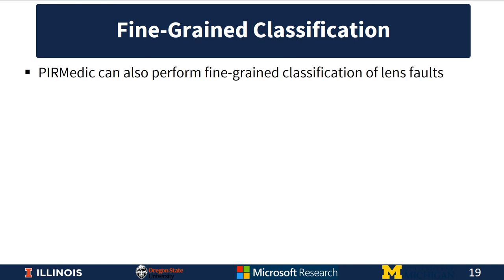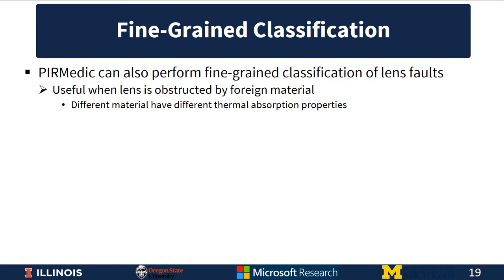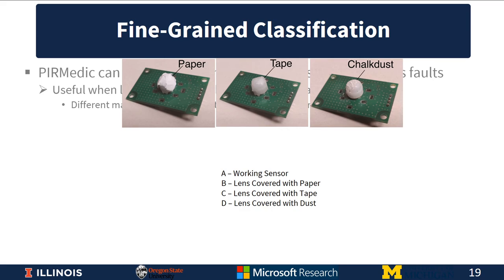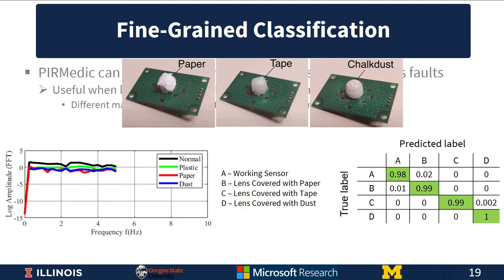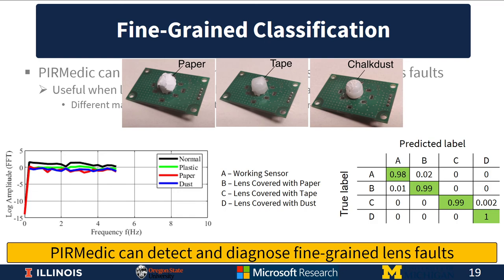PIRMedic can also perform fine-grained classification of lens faults, useful when a lens is obstructed by different foreign materials each with different thermal absorption properties. We consider sensors with lens covered with paper, some with tape, and some with dust. Plotting the frequency spectrum of the analog output shows a deviation between the frequency responses caused by each obstruction. The PIRMedic framework predicts the label of the sensor to a high degree of accuracy and is able to distinguish between each of these causes of lens faults.